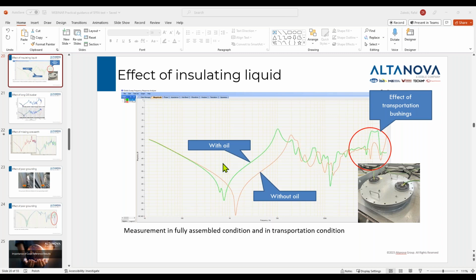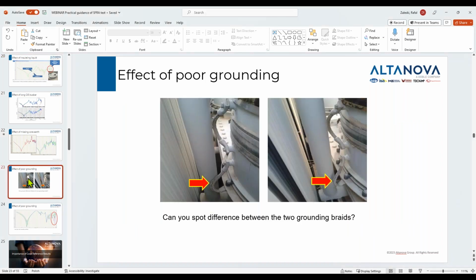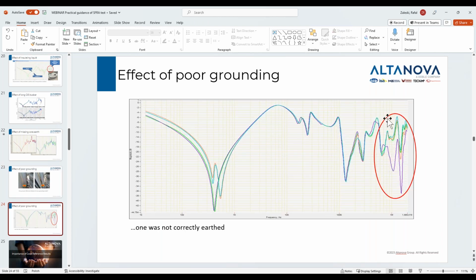Slide 23 left, picture, grounding is touching the metal constant. Aha, okay, now I know what you mean. It is okay, one is touching, one is not touching, but that was not the case. This is not what I wanted to say. My point was that one of these braids was not well grounded anyway. Even if it's touching, the painted metal will still work, doesn't matter. It didn't provide me good earthing points, so the trace was not correct.